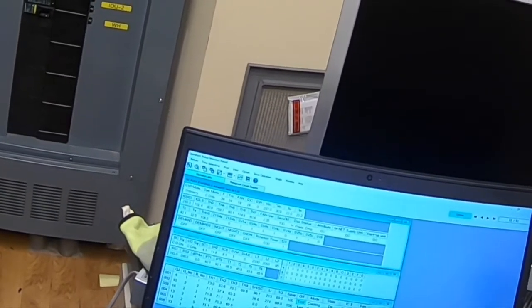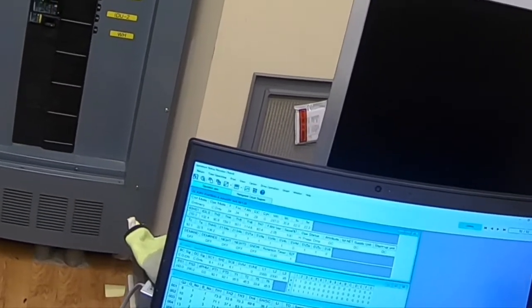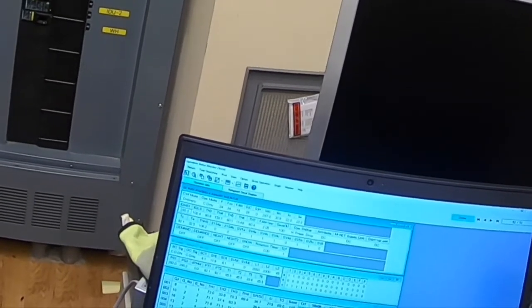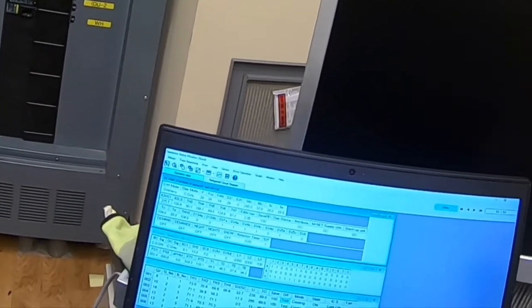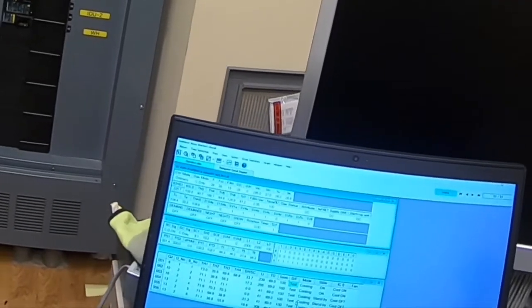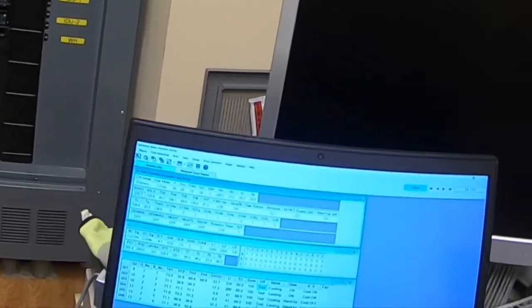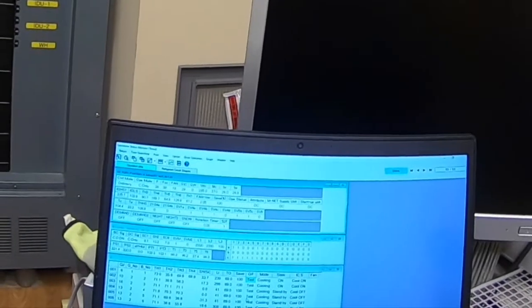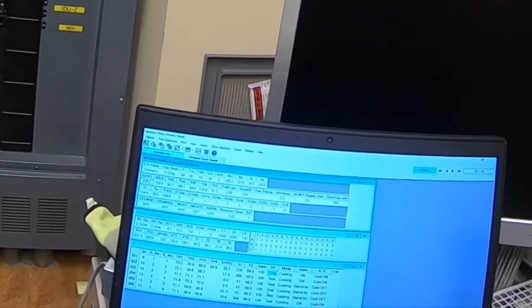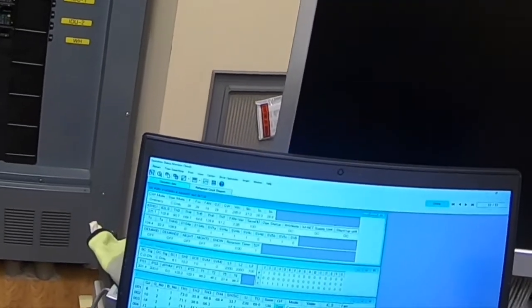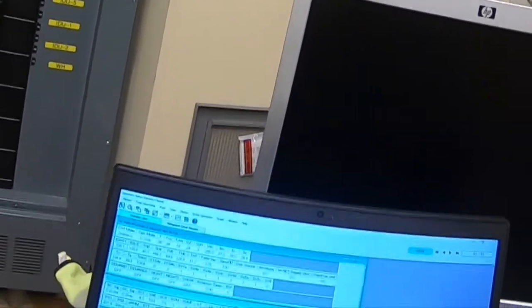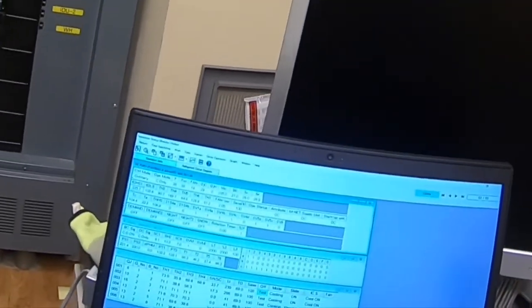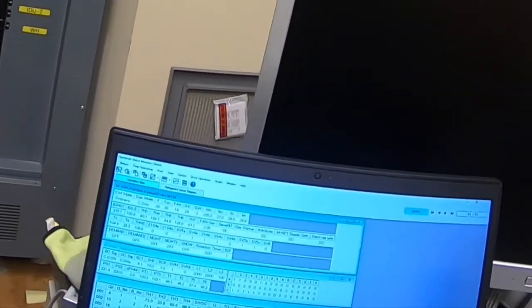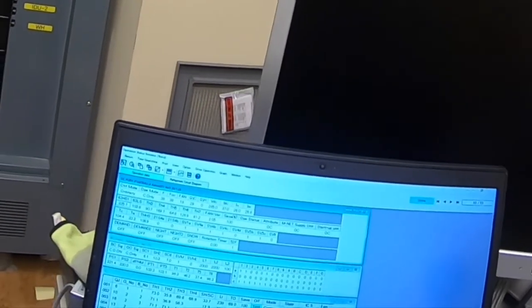But you get a good sense of what's going on. These units are still in standby, they haven't come on yet. Nothing's fast when it comes to these, so I'm waiting to see when they'll come on, and if there's a problem. If they're not coming on, that's a problem. Put them in test mode and they don't come on, that's another issue. So putting it in test mode is going to tell me what's going on with the overall system.